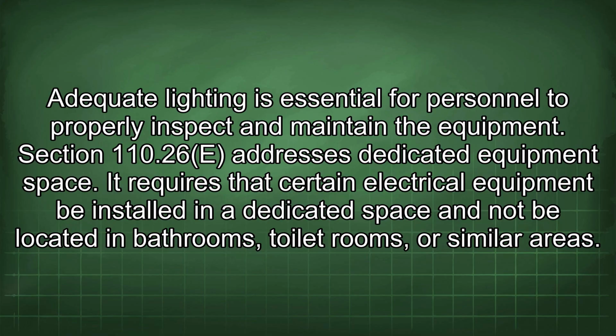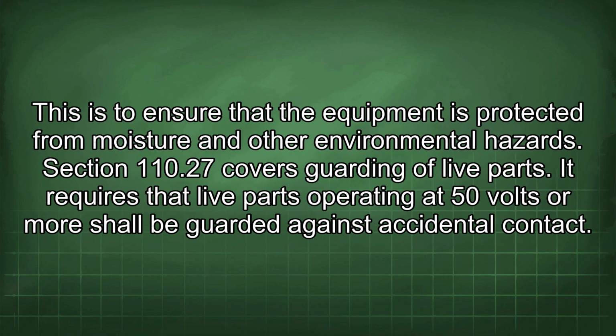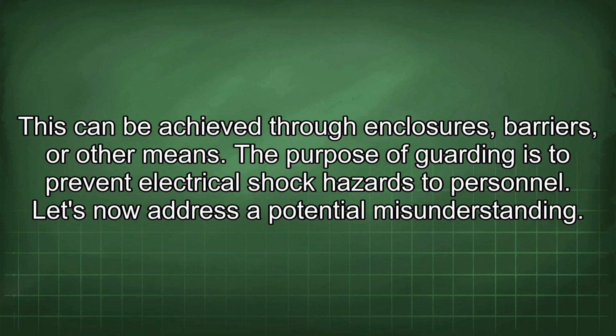Section 110.26e addresses dedicated equipment space. It requires that certain electrical equipment be installed in a dedicated space and not be located in bathrooms, toilet rooms, or similar areas. This is to ensure that the equipment is protected from moisture and other environmental hazards. Section 110.27 covers guarding of live parts. It requires that live parts operating at 50 volts or more shall be guarded against accidental contact. This can be achieved through enclosures, barriers, or other means. The purpose of guarding is to prevent electrical shock hazards to personnel.